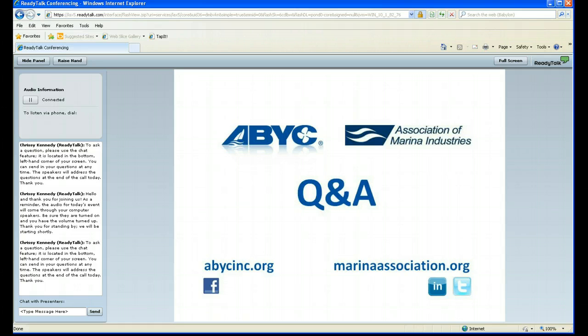Also, Chris has talked a lot and showed pictures of outlets and plugs that have melted. He mentioned faulty equipment. Faulty could mean just a loose connection. Also, it can be caused by voltage drop. If there's a marina owner listening and you're experiencing voltage drop issues where motors sag or lights dim during busy seasons like the 4th of July, Memorial Day, Labor Day or other events, and you're experiencing outlets and plugs melting, it could be problems with the voltage drop, and you really need to check that out and resolve that issue to be able to resolve some of these fire hazards that are out there.